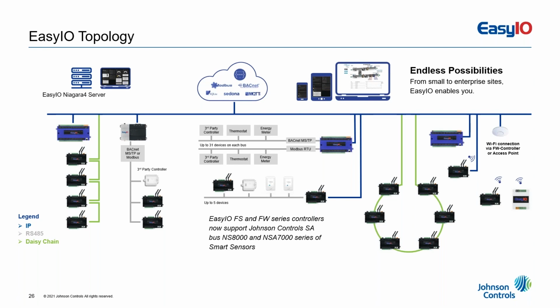At the left side, you see the daisy chain topology. You can use a JACE with legacy drivers to bring connectivity with other systems. You can use the FS to make a BACnet and Modbus network by connecting over 90 devices or more than 3,000 points. That makes it a really, really powerful controller in our industry. Even for small sites, big sites, there are no limits for us. So the FW, as I said, can manage up to 5 devices.